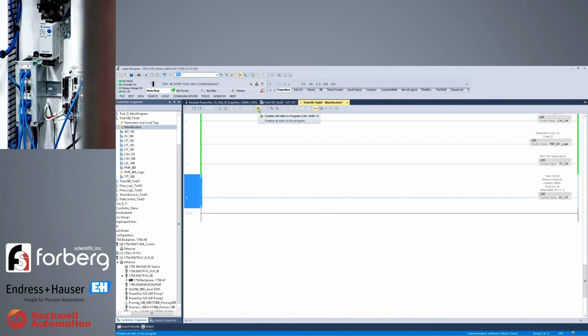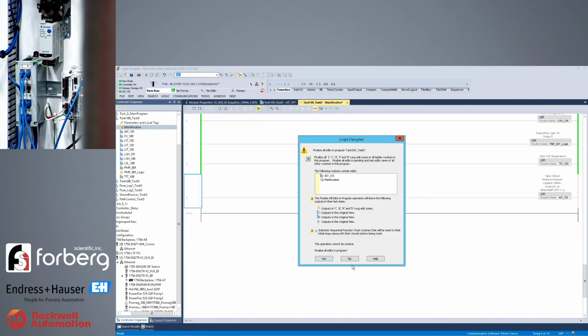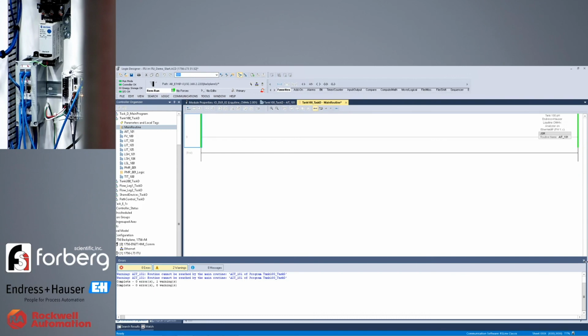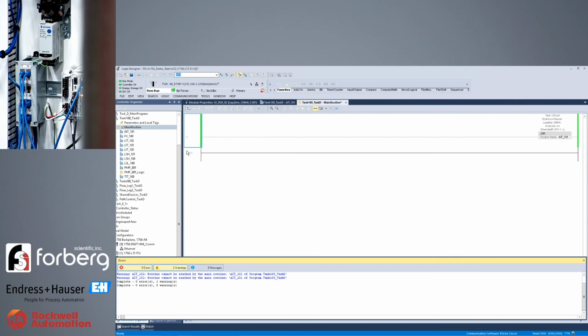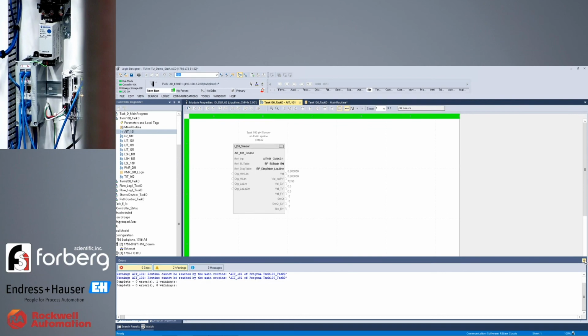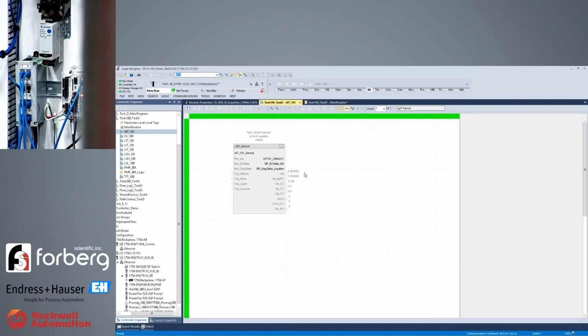So it'll take these couple changes to this routine into the AIT 101. As I jump over to this, we should see the values updating. So before, where they were zeros, now we're seeing the 8.26 and the 72.95 values for temperature. So those values are reading, and at this point, our programming is complete, and we're ready to move on to the operator interface portion of the Plant PAX.